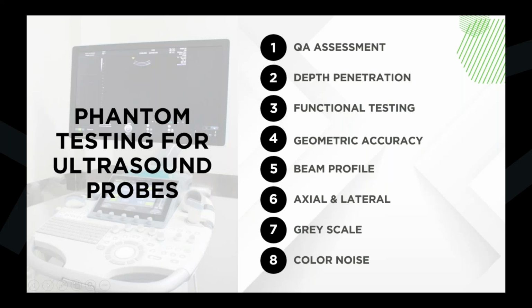The second one we're going to go over is the depth of penetration test. The third one's functional testing. The fourth will be the geometric accuracy test. We'll go over a beam profile test, axial and lateral test as well, grayscale test, and color noise test. We use all of these for all of our PMs. So every time we're doing a PM on an ultrasound system, we have a list of these tests.